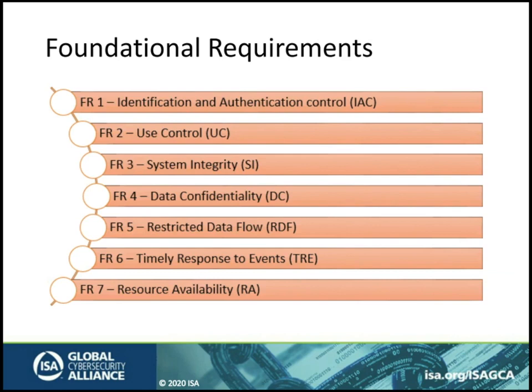Foundational requirements are used to organize the technical requirements in the standards. There are seven of them. The first two, identification and authentication control, and use control, are commonly known in the IT world as access control. The standard split them out in order to manage the number of requirements. Access control is probably the largest number of technical requirements in the set of standards. Then there's system integrity, data confidentiality, restricting data flow (primarily through networks and network control points), timely response to events -- these could be cybersecurity events or alarms and other events from the equipment under control -- and finally, resource availability. So these are the seven foundational requirements throughout the series.